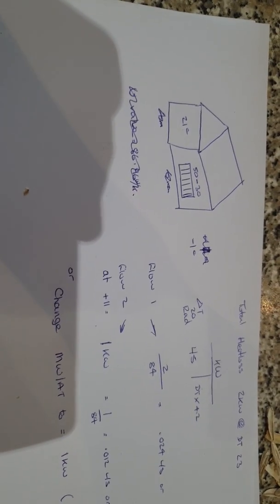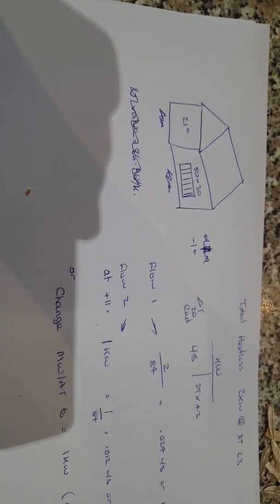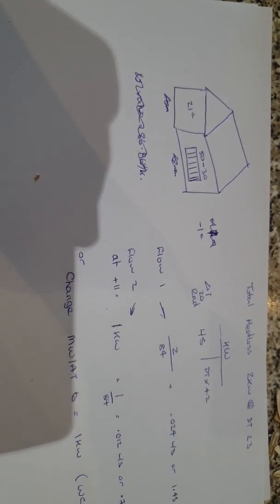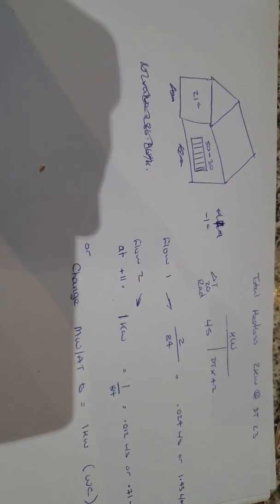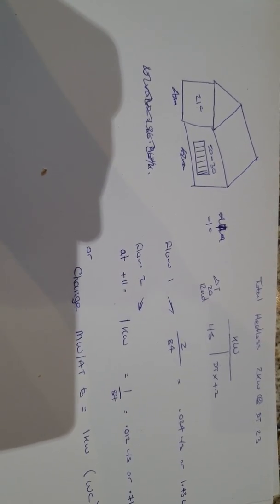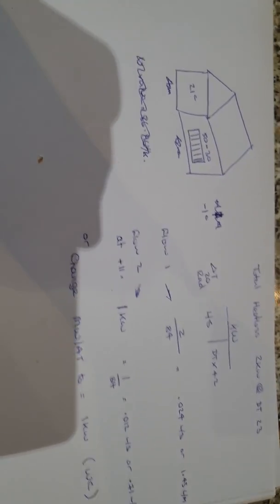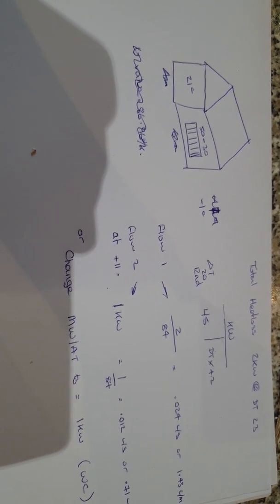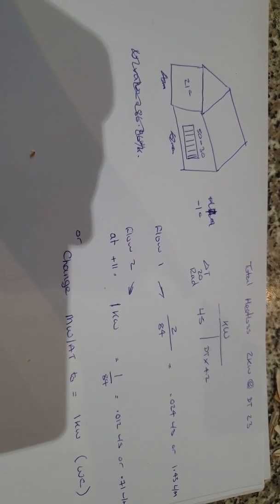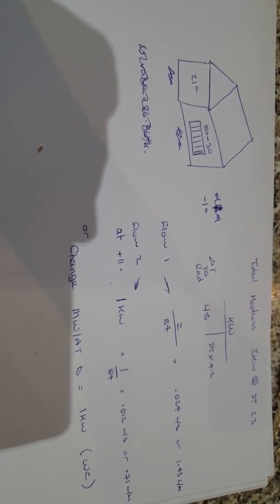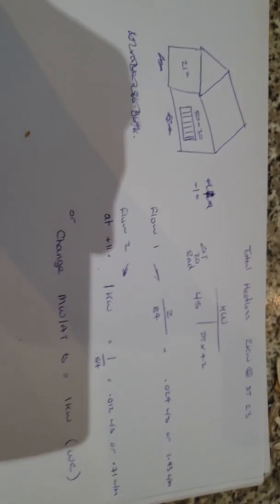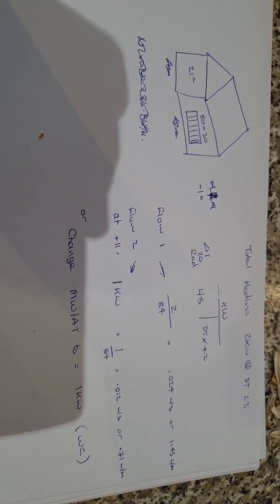By the time I've measured the delta T across that one and possibly adjusted it, all the other rooms are going to be overheating or switching off on stats if we've got stat systems, and we're not going to be able to balance. This really isn't a very practical method of doing it.